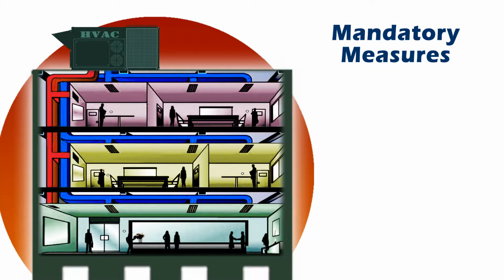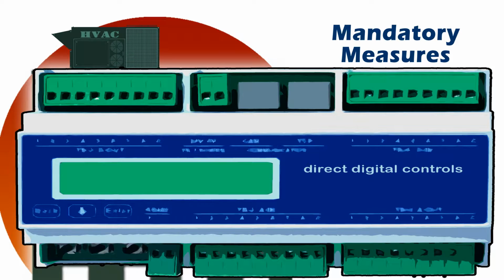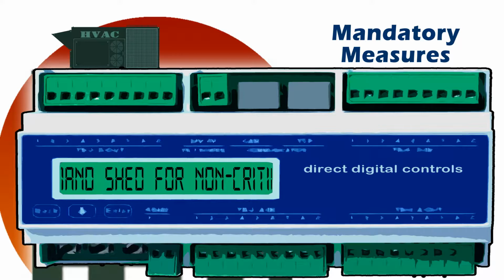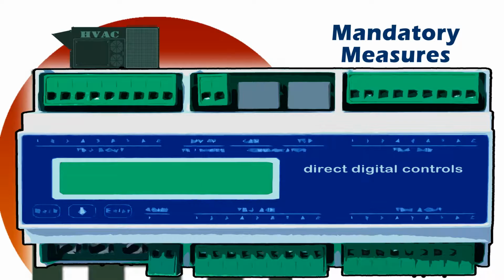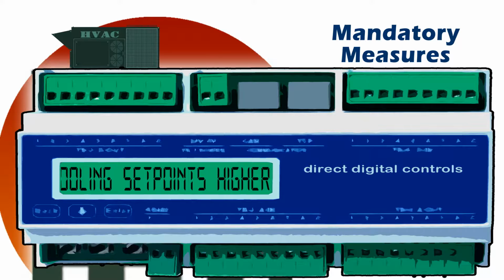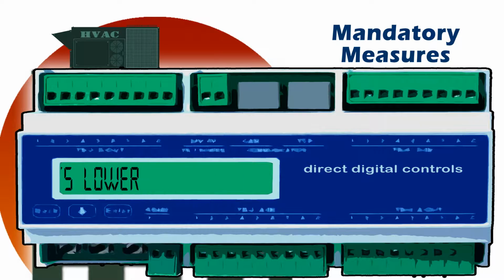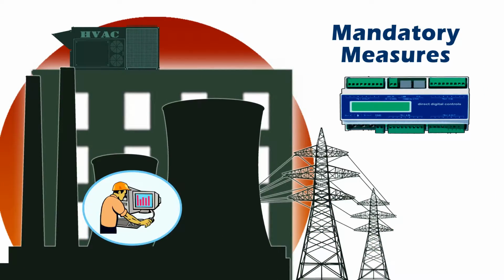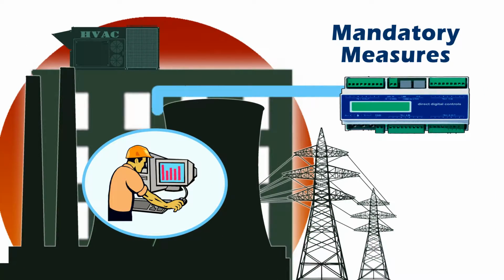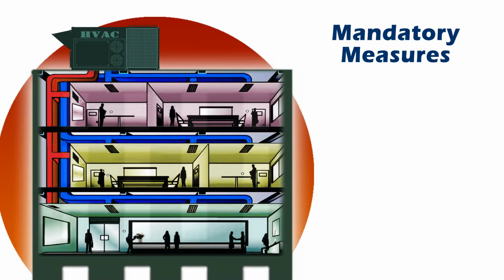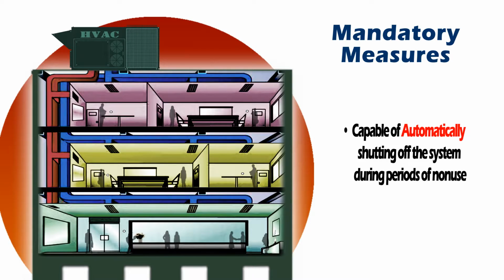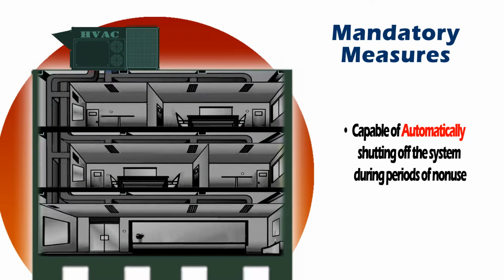In addition, HVAC systems with direct digital controls to the zone level must be programmed to allow a centralized demand shed for non-critical zones. Centralized demand shed controls have the capability of remotely adjusting the cooling set points higher and heating set points lower, as well as receiving demand response signals from a local utility to modify electricity consumption for a limited period. Lastly, HVAC control systems are to be capable of automatically shutting off the system during periods of non-use. The prescriptive requirements include the following.